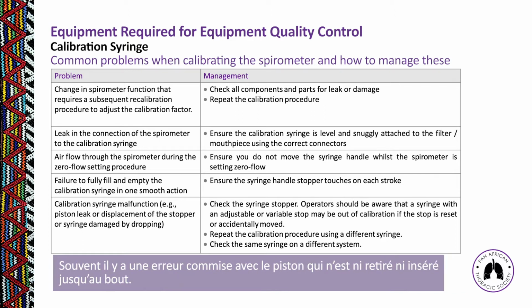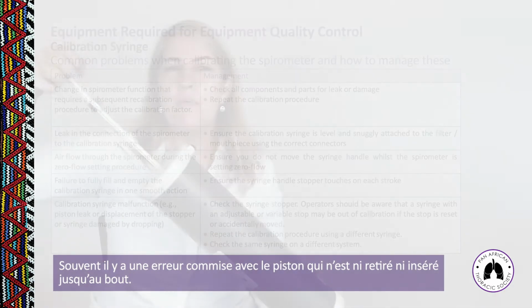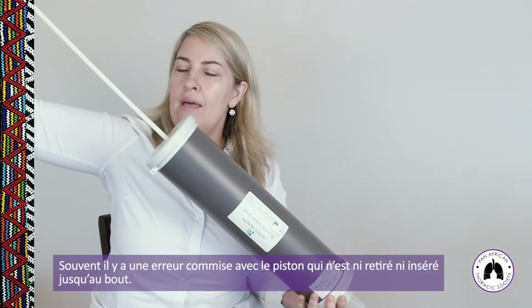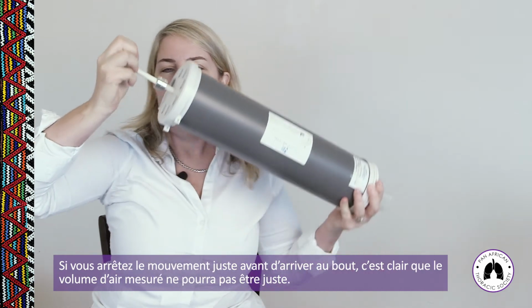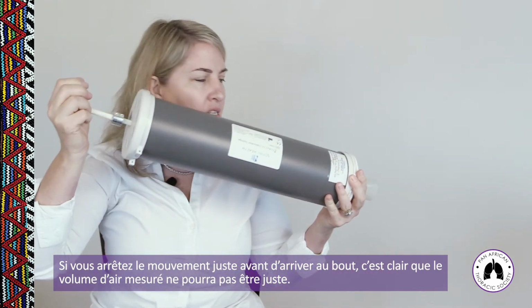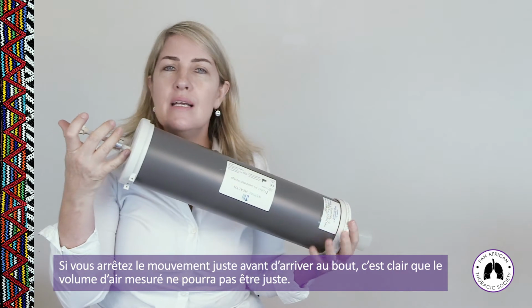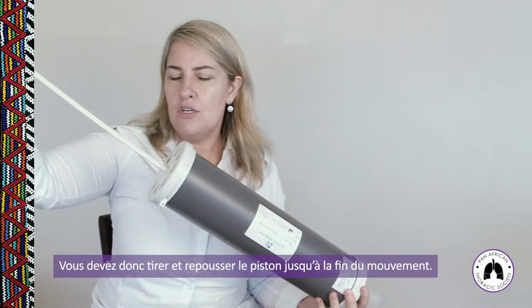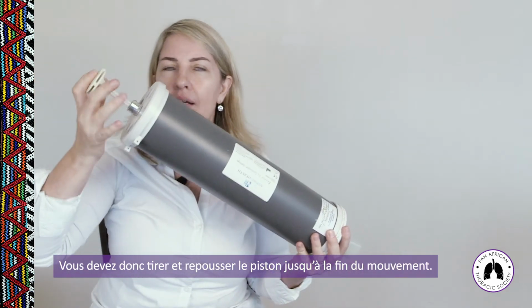One of the things that people do wrong when they are calibrating the machine is that they don't pull out the syringe plunger all the way, and they might not put it all the way in. If you leave a little gap like that, obviously the volume that you're measuring is going to be incorrect. So make sure when you're using the syringe handle that you're pushing it all the way in and out.